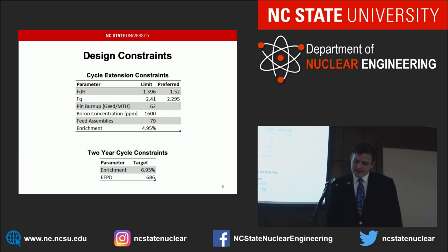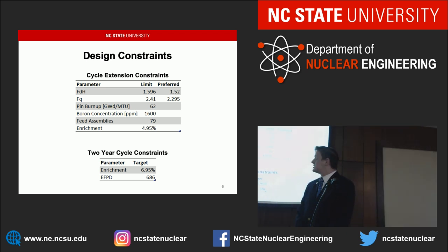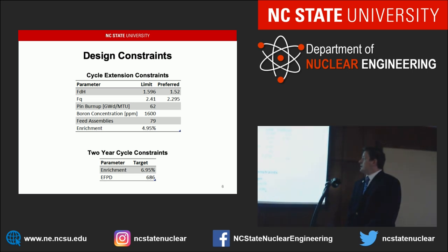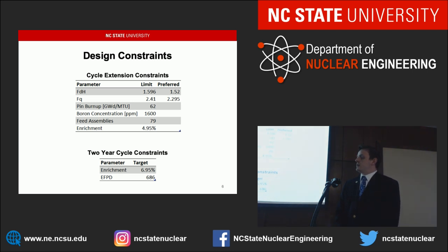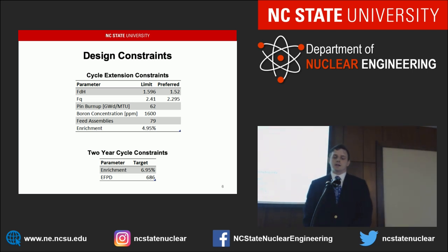One thing about that is the burnup limit is set by the fuel integrity, which is determined by the fuel vendor. So in our case, we're working with Framatome. So that was a given constraint for us. Boron concentration limit of 1600 ppm, which we'll get into a little bit later, but that's not a hard limit. That has more to do with the chemistry of the coolant, because one of our designs actually goes a little bit above that. But we calculated the moderator temperature coefficient, and it is still sufficiently negative.